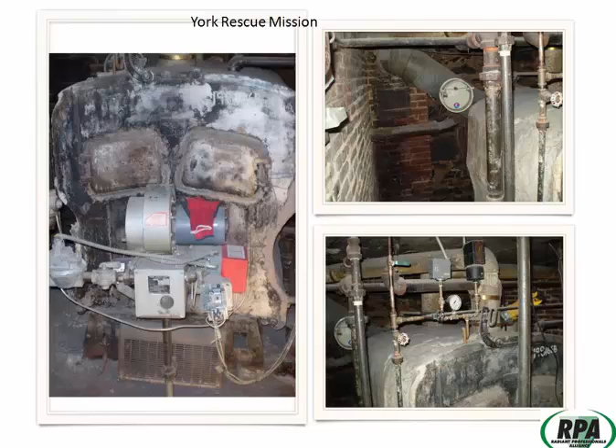So how easy is it to go from steam to hot water? It's actually relatively easy, or you can go from hot water to hot water. In this slide, this was a hot water boiler that had 3 zones. You can see that the water feed's not in the proper location. We're pumping towards the boiler and towards the expansion tank. So it's very easy to make a conversion from a standard chimney vent boiler to a ModCon. Go ahead, Mark, next slide.